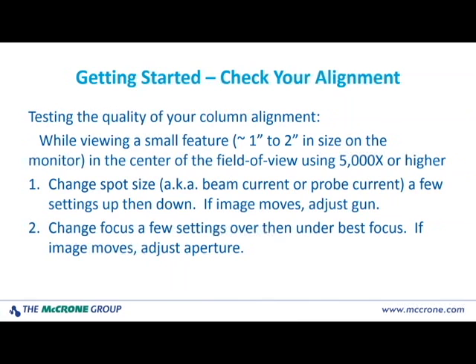The other test is to change your focus — a few clicks above best focus, a few clicks below best focus. Again, watch your image. If it moves, then you need to make another adjustment, and this adjustment is going to be back at your aperture. And of course, anywhere along the way, keep your eye on the stigmation. Stigmation is just stretching of the sample in a preferential direction.